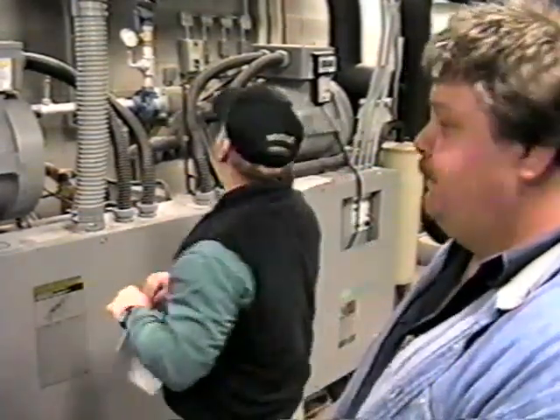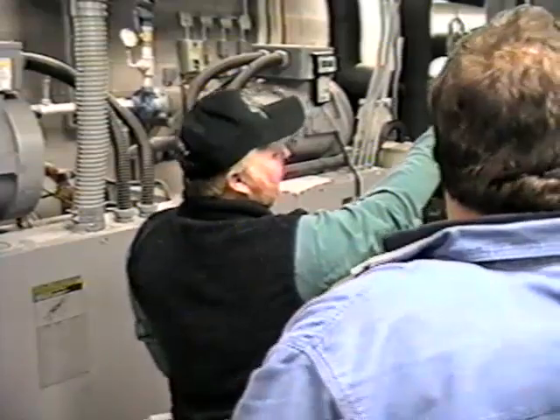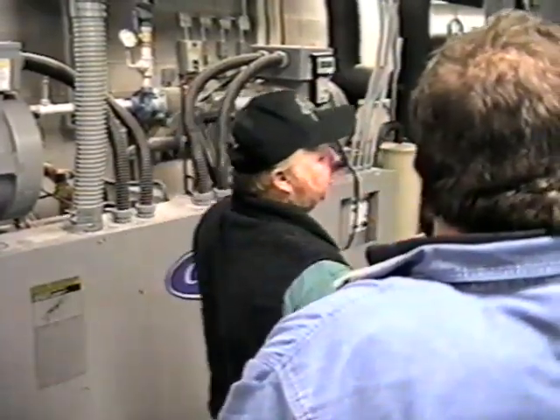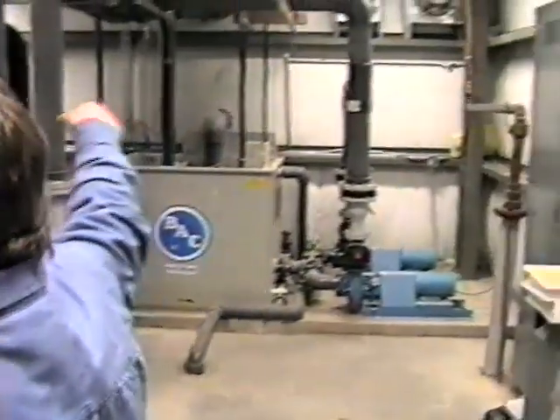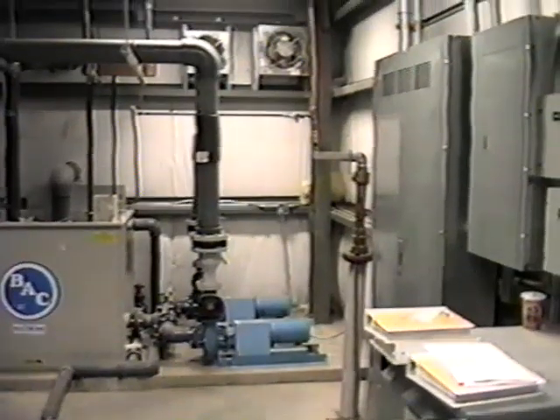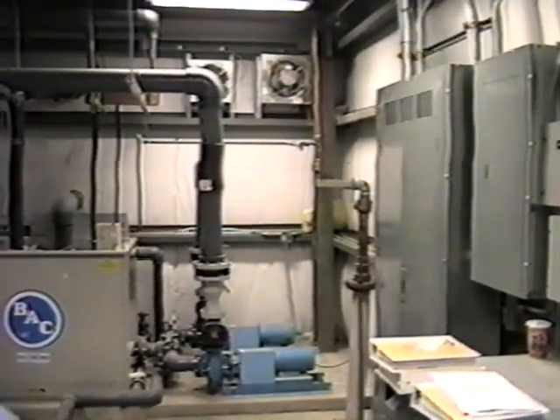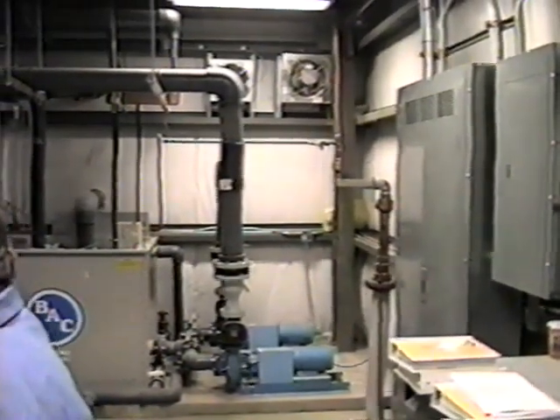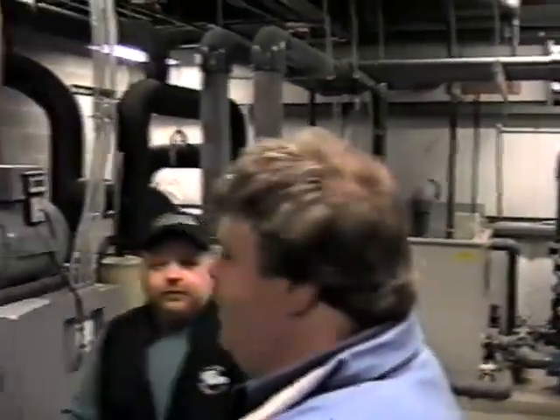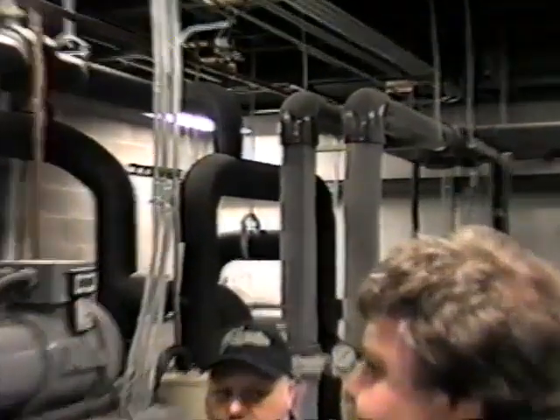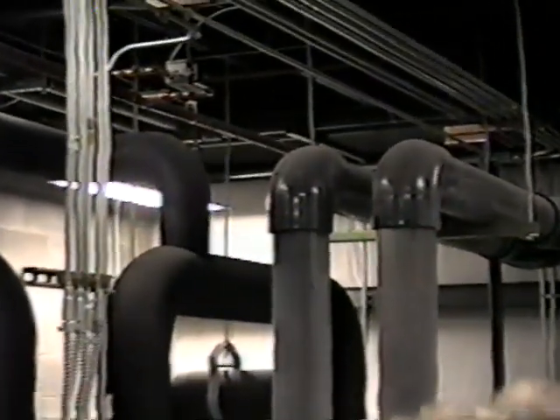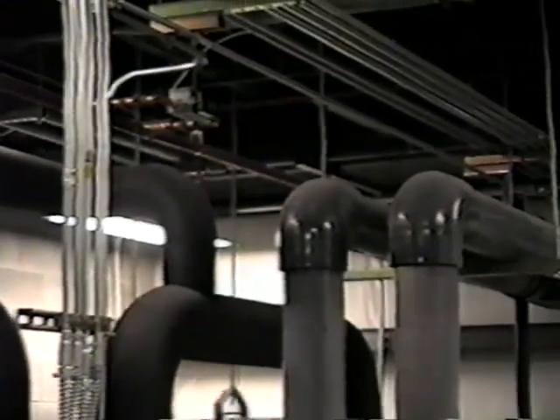And so when that goes on, there's some sort of vent in here? Yes, one of those fans is hooked to the refrigerant alarm, and that sucks everything out of it. Right, it's going to attempt to anyhow. It depends on how large the leak is. And so if we do have a remote alarm outside, I would not be totally scared that something real nasty is happening. You can open the door and see what it looks like in here.